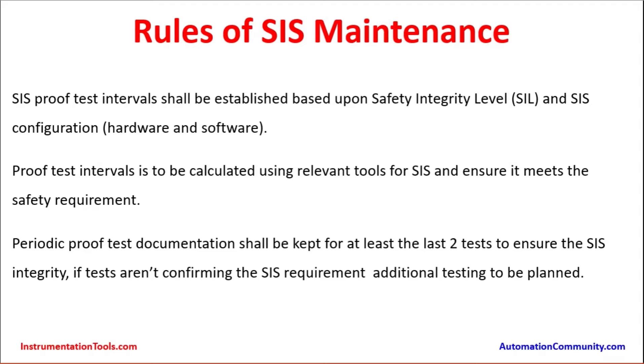Periodic proof test documentation shall be kept for at least the last two tests to ensure SIS integrity. If tests confirm the SIS requirement is not met, additional testing is to be planned. If any instrument fails the test, the root cause of those failures needs to be identified and corrected.